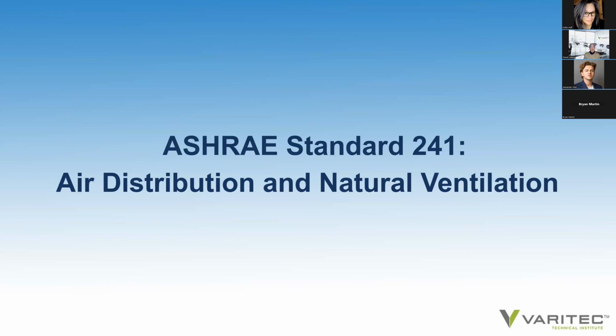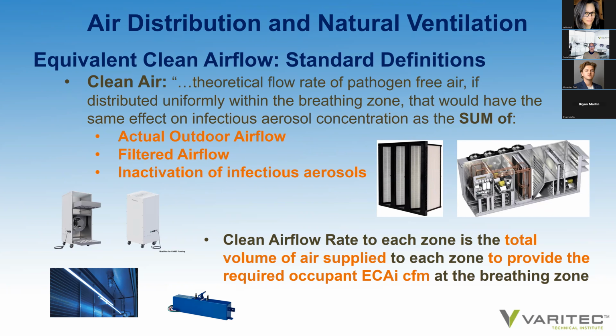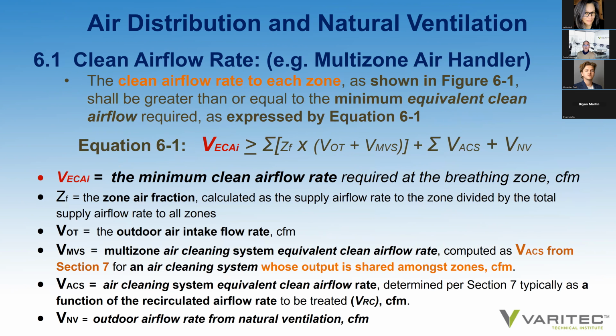So let's look at the section of air distribution and natural ventilation. And we're going to look at clean air, that is to say, air free from infectious aerosols. So in order to understand how much clean air needs to be provided to each zone, depending on the effectiveness of the air cleaning technologies in removing infectious aerosols, this is the purpose of this section. How much air needs to be supplied depending on the technology applied to reduce the risk of infectious aerosols being propagated to the zone.